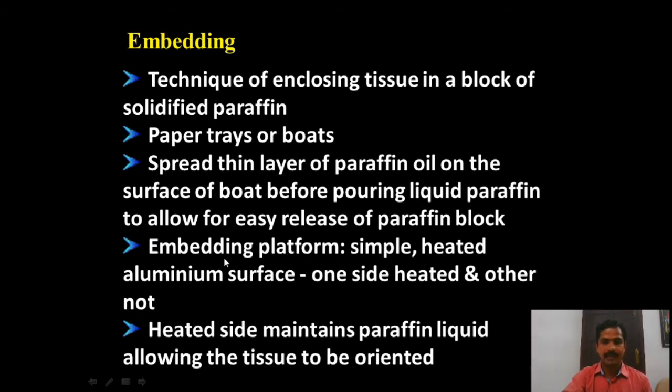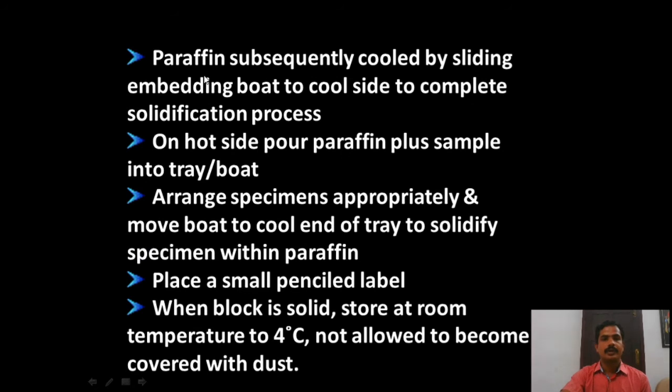It is just a platform. It is a simple heated aluminum surface, just like a table, one side of which is heated and the other side is cool. The heated side maintains the paraffin liquid, allowing the tissue to be oriented. The paraffin is subsequently cooled by sliding the embedding boat to the cool side to complete the solidification process.